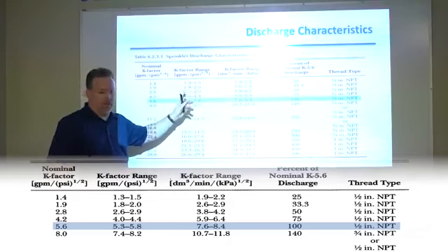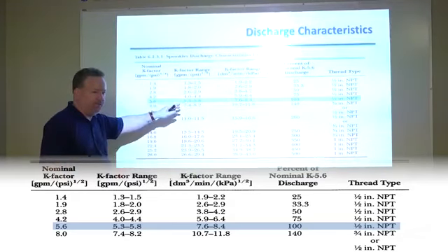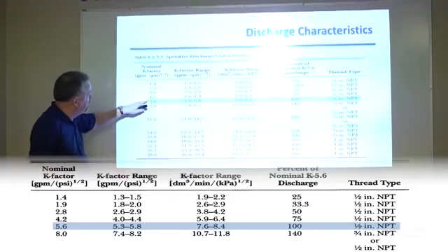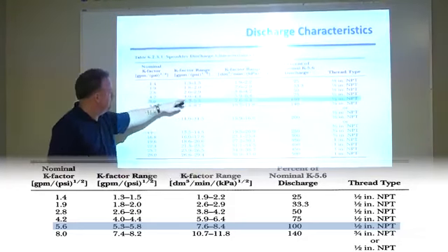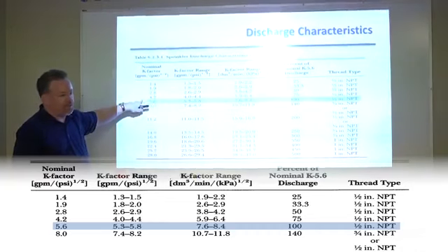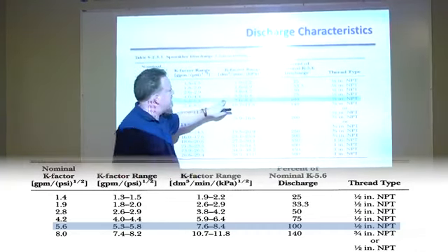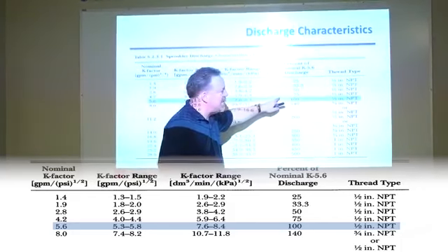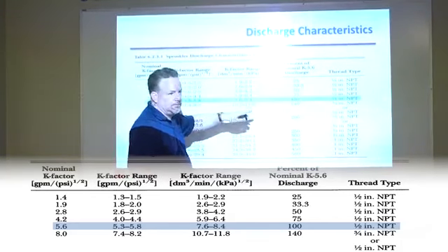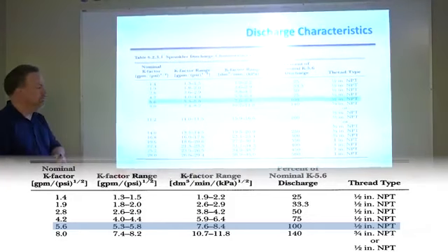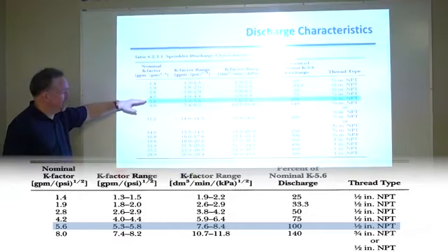That's where we saw the VK 472, which is a 5.8. So that's in the range of a nominal K5.6. Okay? So this is basically the baseline flow, 100%. This is our baseline flow.